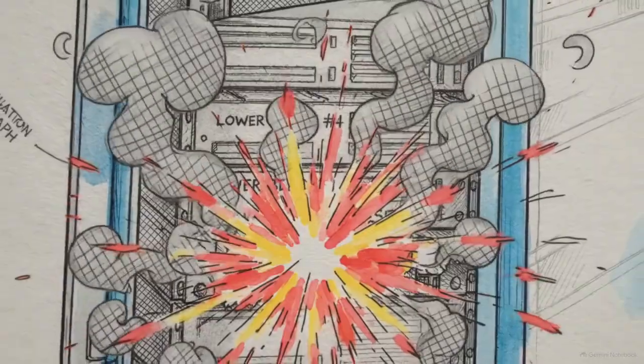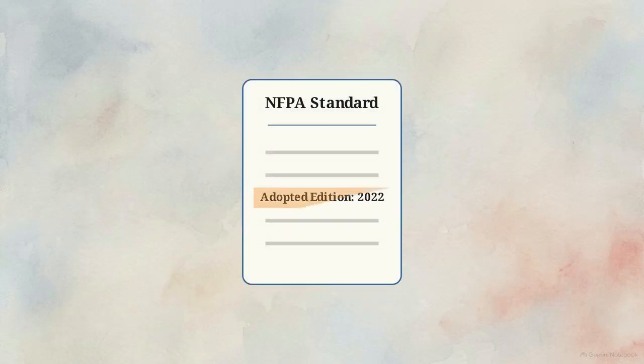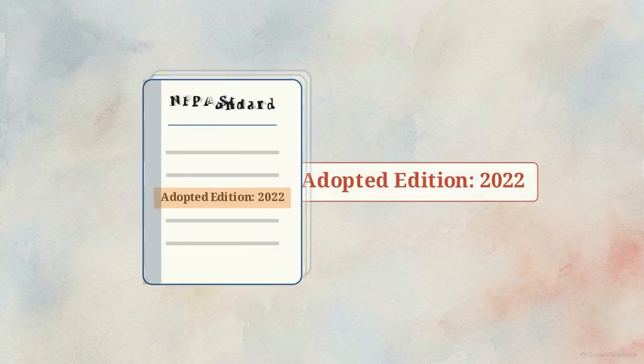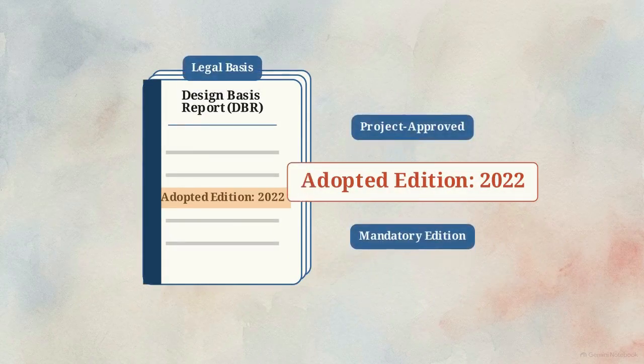A single spark in a server rack can escalate into a massive thermal event in seconds. When this happens, a facility manager's first defense is often pointing to a binder that says the data center was built to the latest codes. But specifying the latest standard in a contract offers no protection on its own.